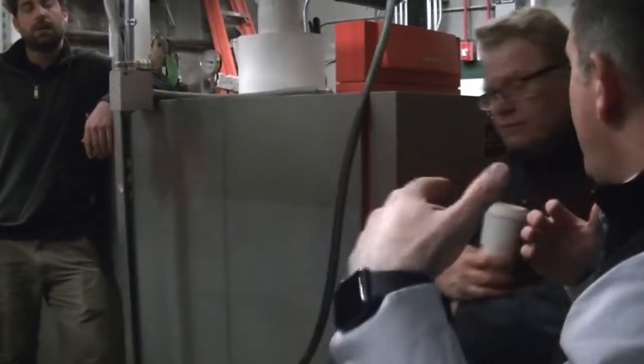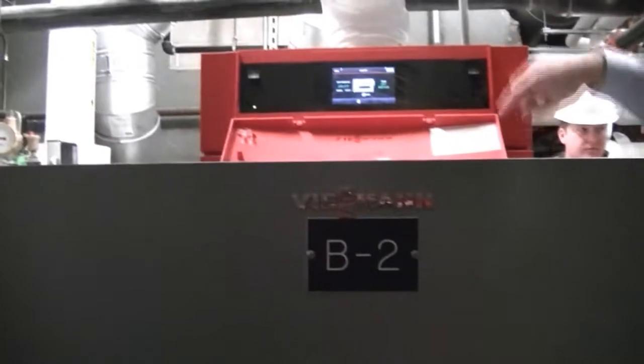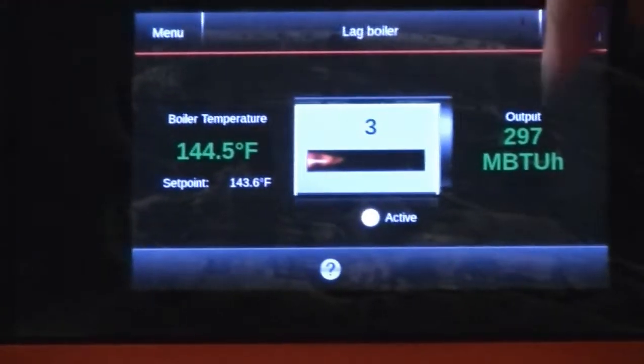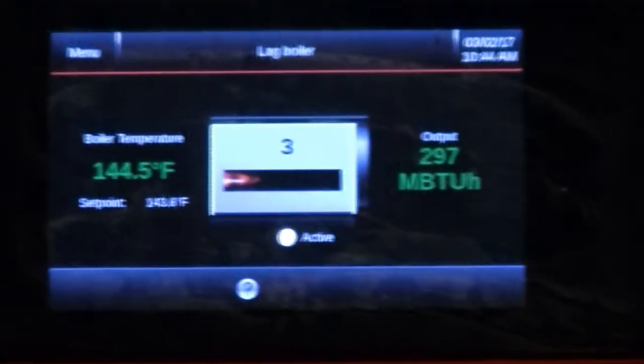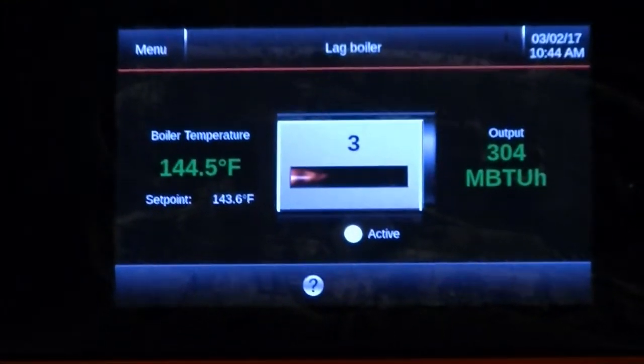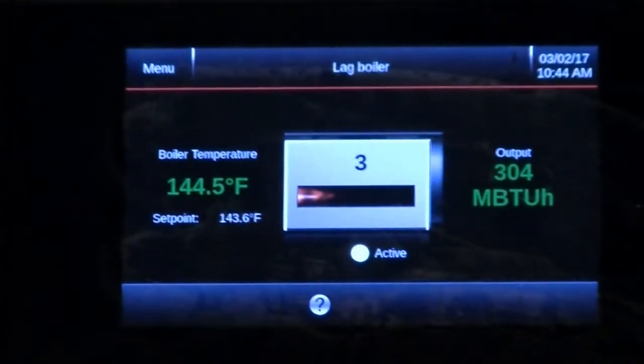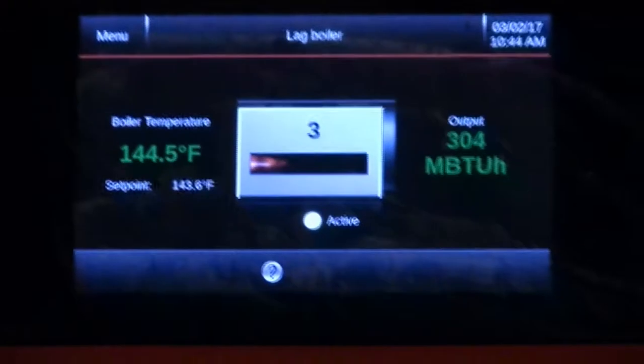All the boilers, except for boiler 1, you'll see what that individual boiler is doing. So if we look here, this one is a second boiler in line, but it's boiler number 3 as far as our control knows. You'll see that it's firing because there's a little flame in the window. So that boiler is actually running. You'll see that it's running at about 144 degrees, and its output right now is about 297,000 BTUs. Okay, so it'll give you the modulation point, it'll give you the temperature that it's running at.